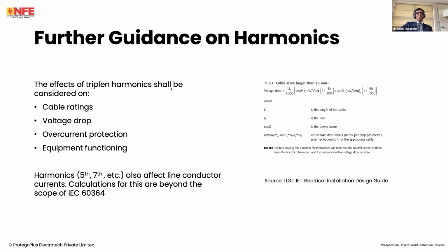The actual reading of the standard has to be done by yourself. It affects the cable ratings, voltage drop, overcurrent protection, and equipment functioning as well. However, we only spoke about triplen harmonics, which are the third and multiples of the third. If you have harmonics of the fifth, seventh order, etc., they even affect the line conductor currents. These are beyond the scope of the 60364 series. There are other standards to look at for these.